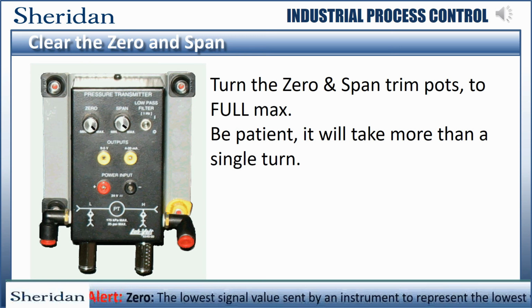Once the transmitter is mounted, zero out or clear the transmitter's zero trim potentiometer or trim pot and the span trim pot by rotating them clockwise until they stop turning. This may be 3 or more complete revolutions. Do not manhandle the trim pots, as this can affect their sensitivity and damage them.